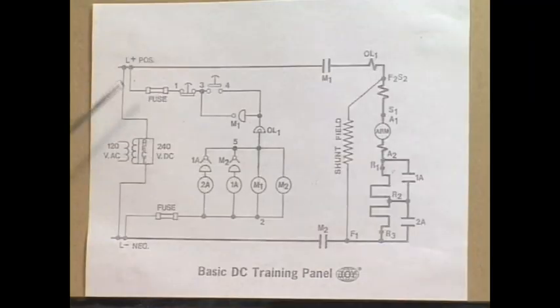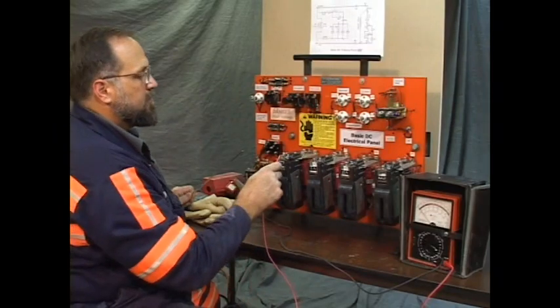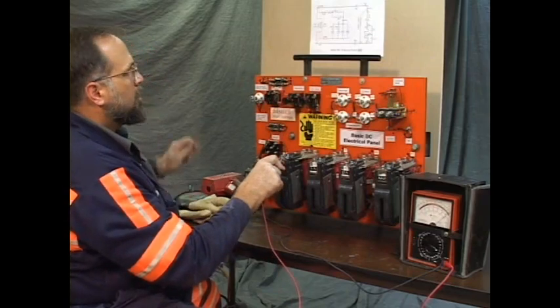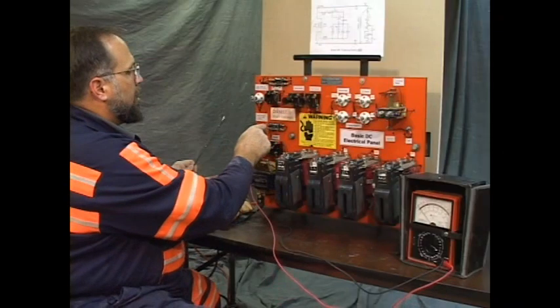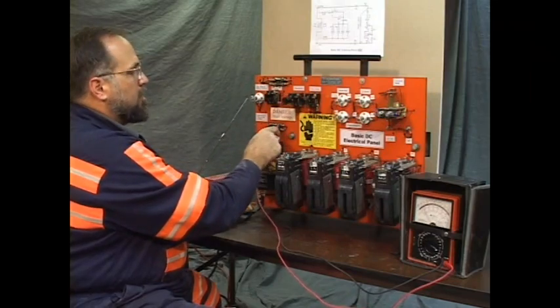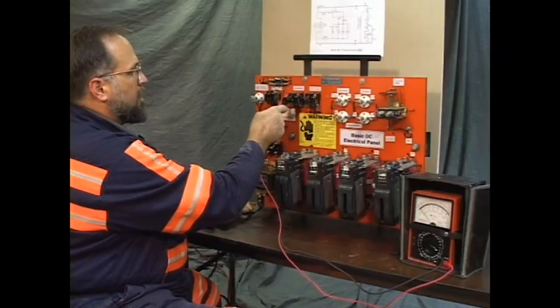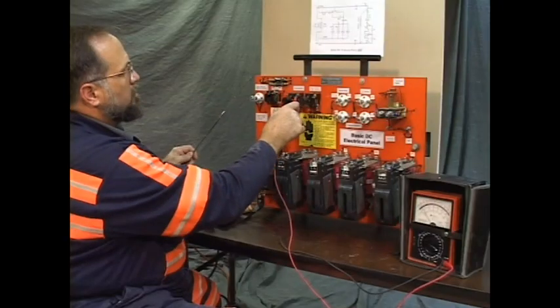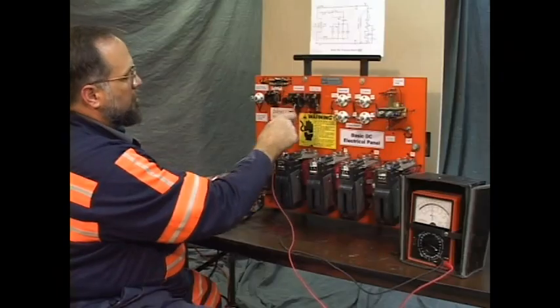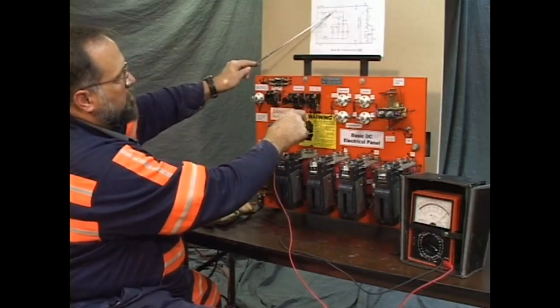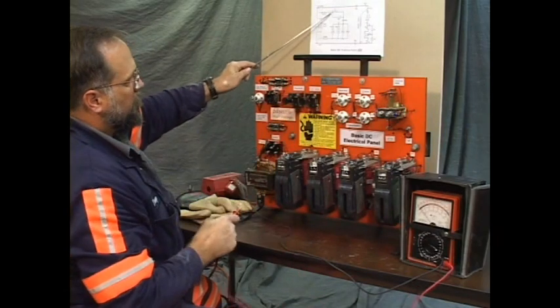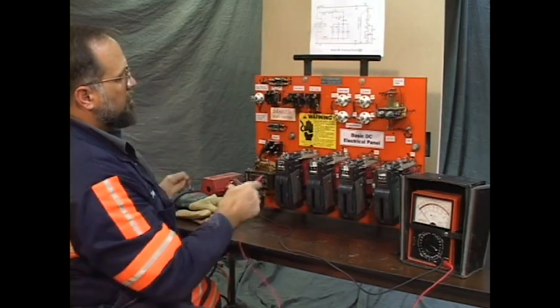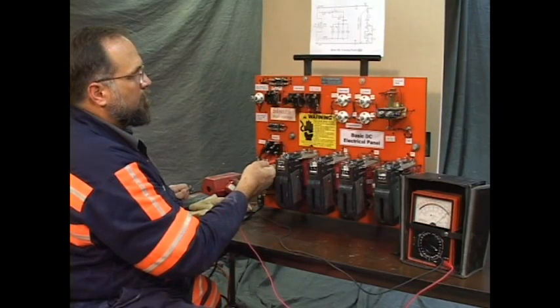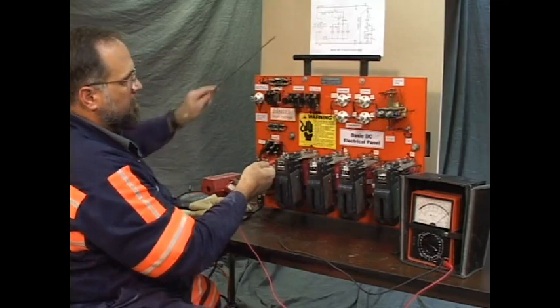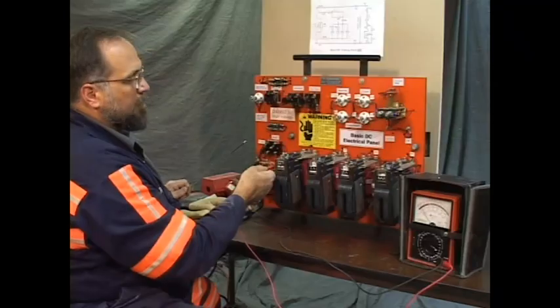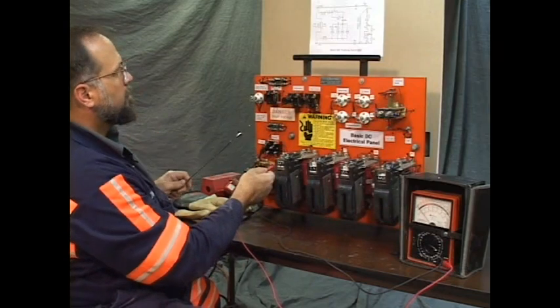Start and follow. I've attached the probe here. First position, the top front of M1. Next position, line side of the positive fuse. Load side of the positive fuse. Line side of the stop switch. Load side of the stop switch. Line side of the start switch. Now, I don't want to pass this. I want to go ahead and check it to the line side, or the top of the M1 mercury tube. The mercury tube is to be open. It's illustrated as an open. I'm going to check to make sure that it is, and my meter indicates that it is open.